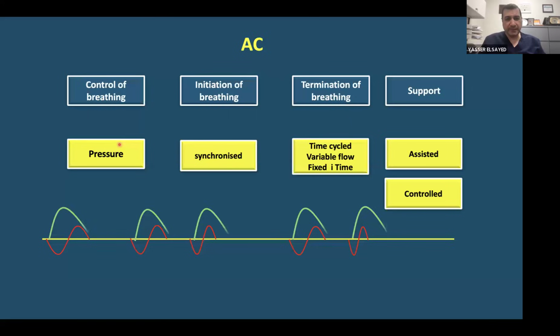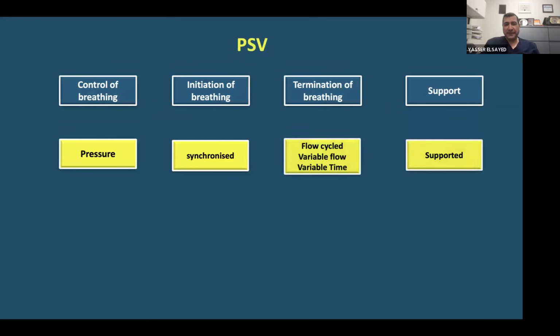So control of breathing is by pressure. It is synchronized at the beginning, but not synchronized at termination. It is time cycled with variable flow, and the I time is fixed. It is assisted. Every single breath is assisted by the machine. That's why it is AC, assisted control. Every single breath is started by the patient and assisted by the machine and totally controlled by the machine, which is different from PSV.